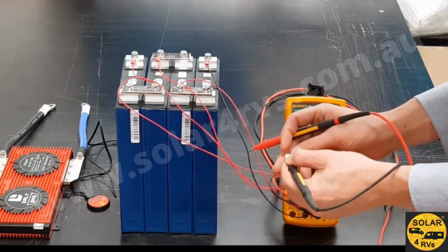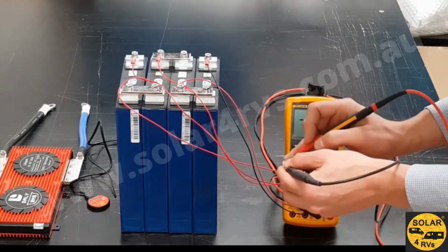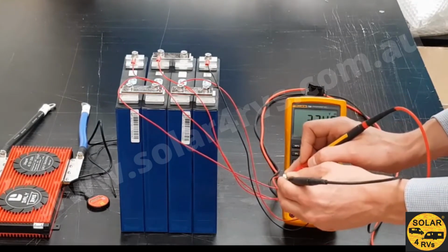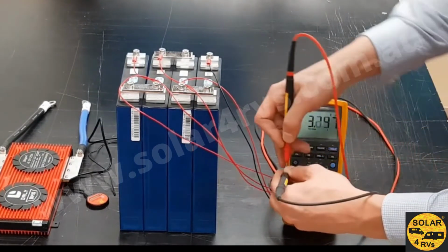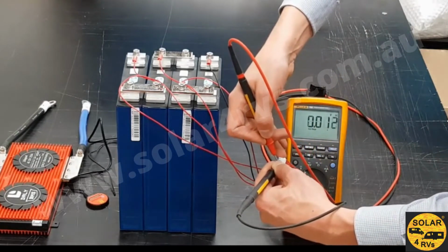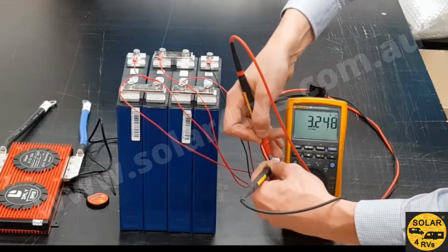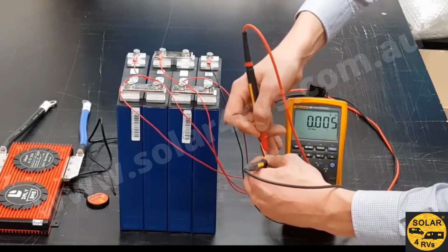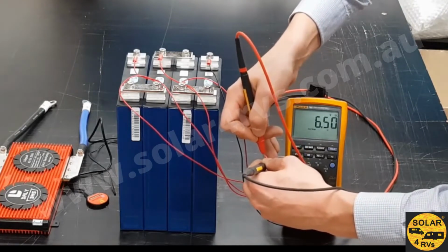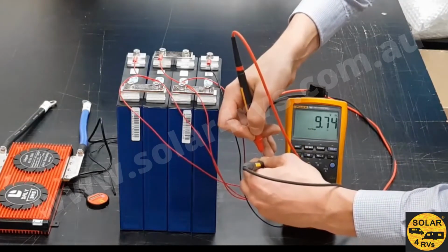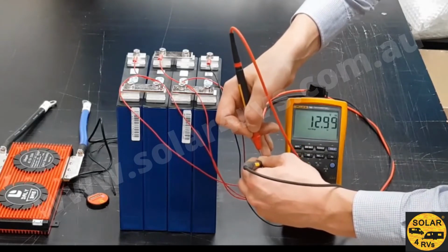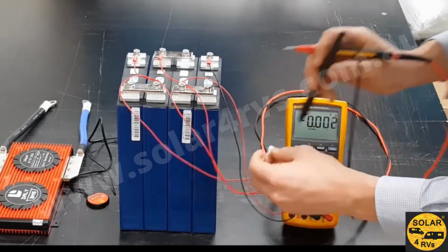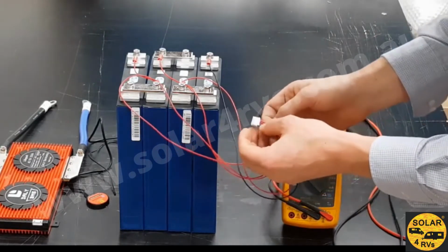So there's my black lead on the pin on the black cable, and then following the adjacent red pin, you can see that we get roughly 3.2 volts. The next one 6.5, 9.8, and 13. So that indicates that the voltage is moving up linearly.